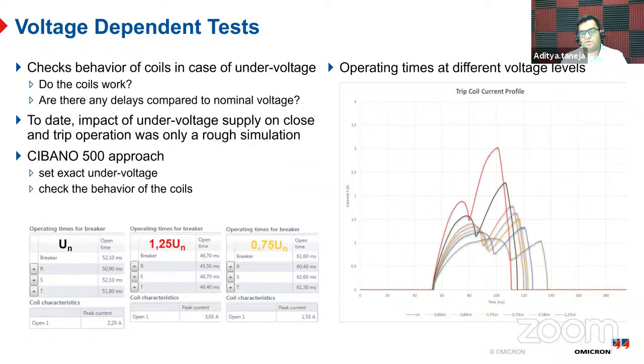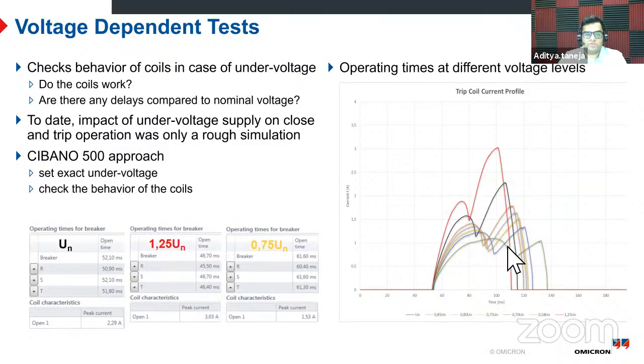The other powerful thing, which I frankly believe more, is to do the testing in under voltage and over voltage condition for the trip coil. There is a lot of text on this slide, so I will just focus on this picture for simplicity's sake. So these are the coil currents which were coming at different voltages. So we did at UN, that is the nominal voltage, at 85%, at 80%, 75%, 70%, and also at 125%. So all of them we did and superimposed them on each other.